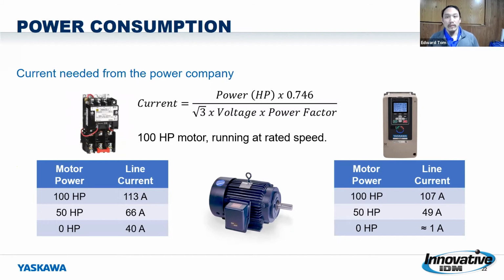So a quick question: is the line current change appearing in reactive power instead of real power? And the answer is yes. When it comes to the current changes, you're always going to have the magnetizing current inside the motor. That's always going to be present in the motor, and on the line side, that's always going to be present. You're always going to see that on the line.